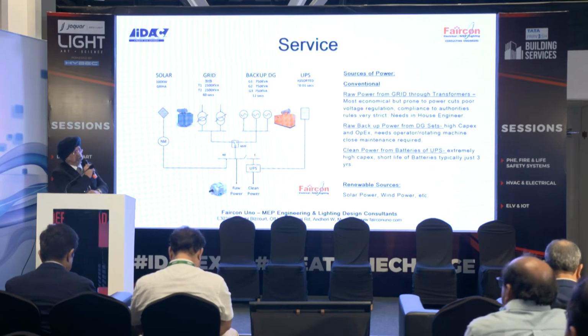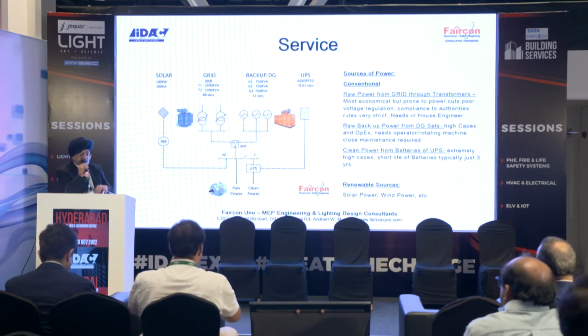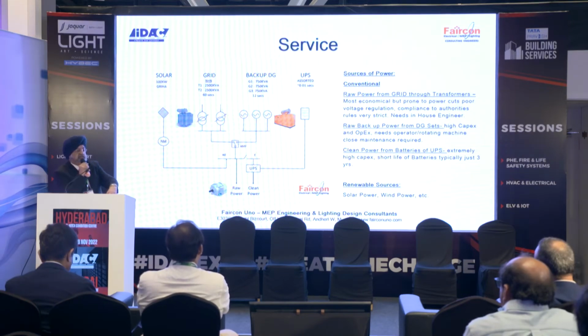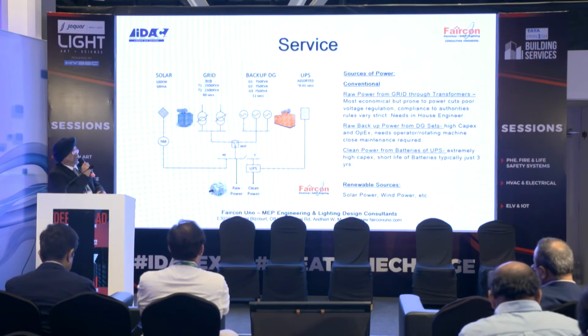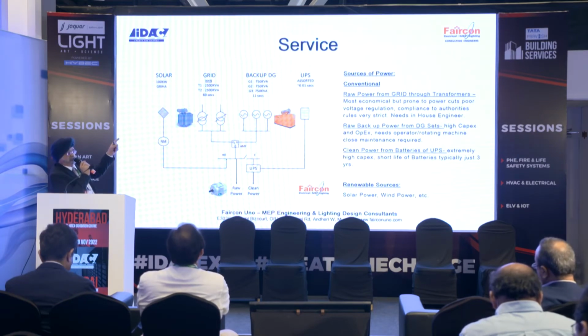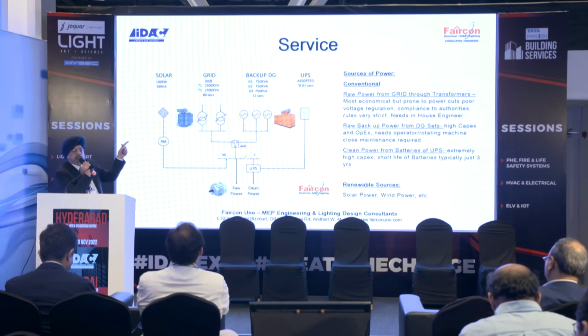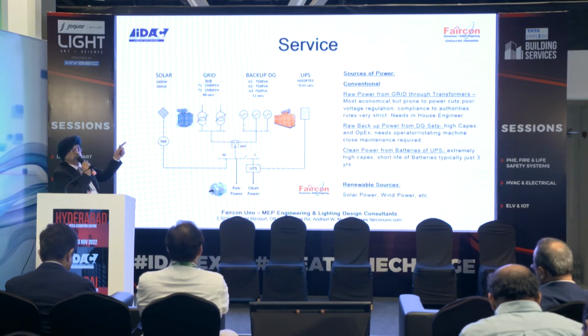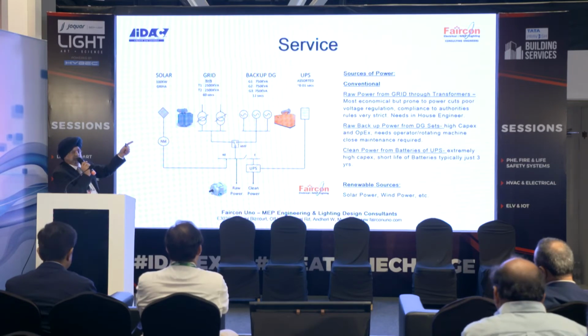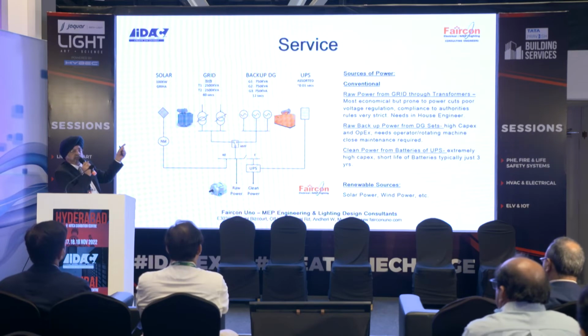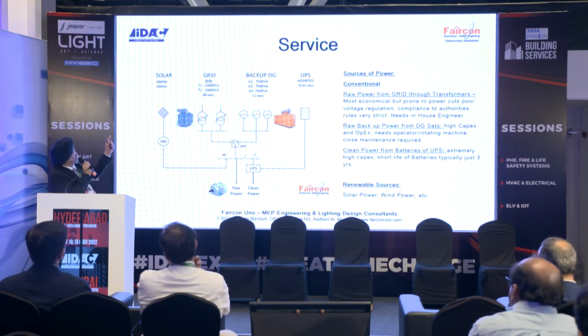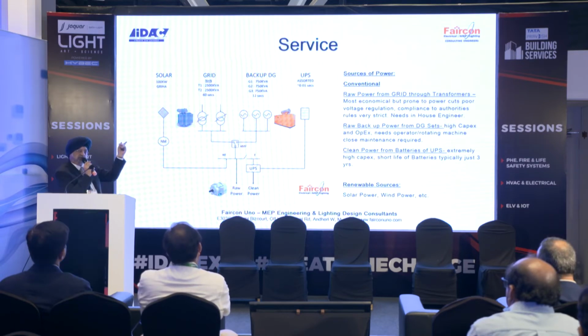The service part is the first thing to be considered. In the service are the sources. See, this drawing tells you basically the restart time. See, the grid power, once it trips, you need at least 60 seconds to set it right again. Backup generator on AMF will need minimum 12 seconds to build up voltage on the terminal. UPS requires less than half a cycle. So it is the quickest one. So that will decide what feeds what. Because the cost is also going up from grid to DG to UPS in the same direction. So you cannot use UPS for any and every load.